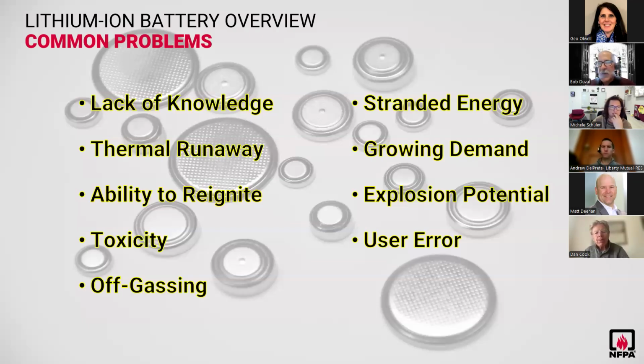This stuff is extremely toxic because of the chemistry being used in there. When it off gases, it might not catch fire, but it will off gas. That gas is extremely dangerous to bystanders and the fire service. The breathing apparatus is 110% required anytime you're dealing with these things from the fire service. Decontaminating your equipment and your PPE is very important after fighting one of these fires as well.